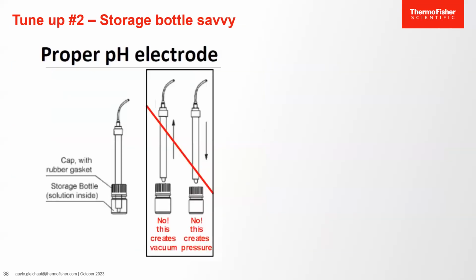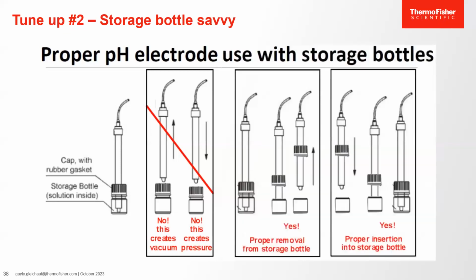Because a picture is worth 1,000 words, here's a graphic that shows how this works. Remember to never push or pull an electrode into a closed storage bottle, as this creates a vacuum or creates pressure. When removing the electrode, open the bottle first by unscrewing the storage bottle, taking it off. Slide the cap to the top of the electrode so it's out of the way, or slide it off the bottom to remove it. When replacing the electrode, first slide the cap toward the end of the electrode and then screw the storage bottle onto the cap. Avoid pushing or pulling the electrode once it's sealed in the bottle.